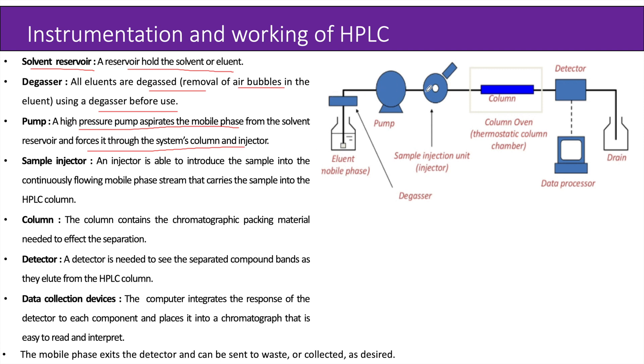The main purpose of the pump is to send the solvent or mobile phase or eluent at high pressure into the column. Then comes the sample injector. An injector is able to introduce the sample into the continuously flowing mobile phase stream that carries the sample into the HPLC column. The main point to keep in mind is that the injector is not putting the sample directly into the column, but is injecting the sample into the solvent stream that has been created by the pump at high pressure.